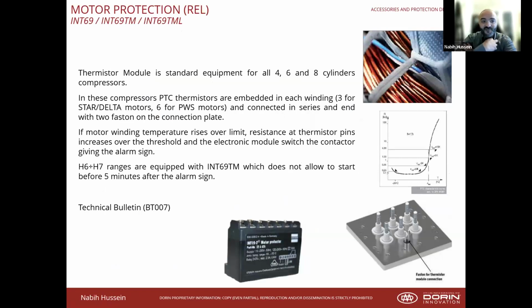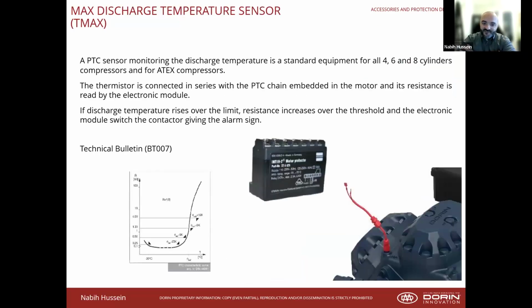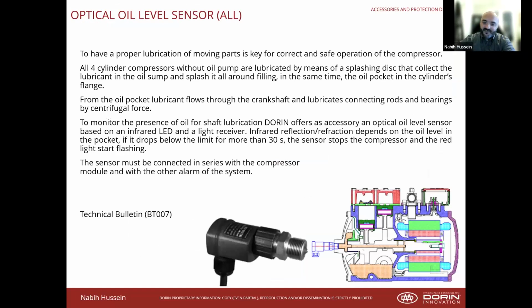So typically, the Kriwan INT69 motor protection will be installed on every compressor. It seems to be what has come out as the industry standard. It's a PTC sensor that's embedded in each of the windings. Once you reach a certain temperature, it turns off the compressor. There's a max discharge temperature sensor, similar functionality, but now it's set off of a max discharge temperature. If it's a smaller compressor and it doesn't have an oil pump, it's going to be using an optical oil level sensor. So it's looking at the little pocket that's holding the oil next to the splasher disc. If it sees oil, it's fine. If it doesn't see oil, it turns off the compressor.